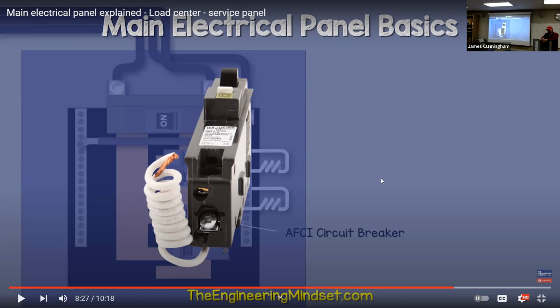I feel like a lot of people don't do that, even with the sub panel. Where it's really required is in sleeping rooms, hallways, bathrooms, and lighting circuits. Then for a living room or something, they'll use a regular breaker. Or they'll use GFCI plugs instead of having the arc fault GFCI. They'll do it that way.